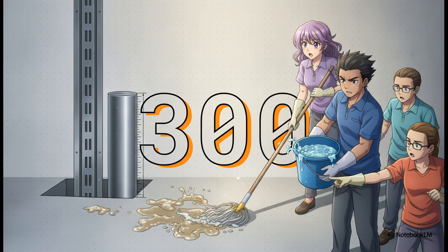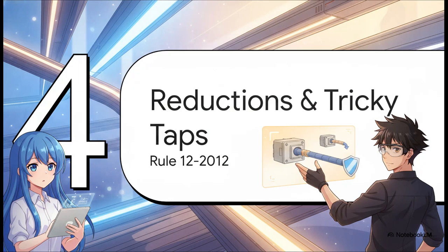And here's your next magic number, 300. If you are punching a busway vertically through a dry floor, it must be totally enclosed where it passes through the floor itself, plus an extra 300 millimeters above the floor just to be safe. Why 300 mil? Well, when the cleaning crew comes rolling by with a sloshing mop and bucket, you really do not want dirty water splashing up and dripping straight into a ventilated busway enclosure. Next up, Section 4. Reductions and tricky taps.